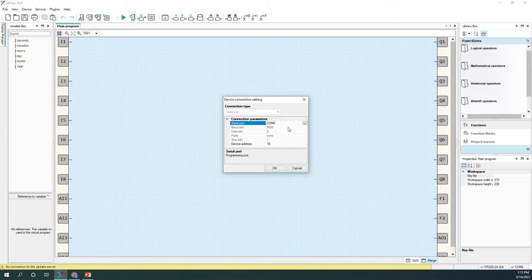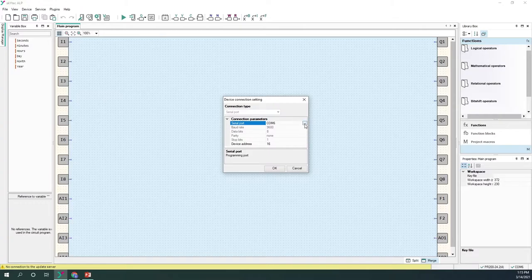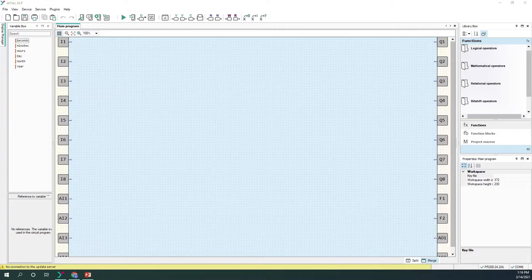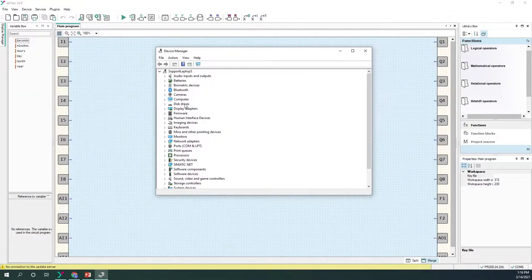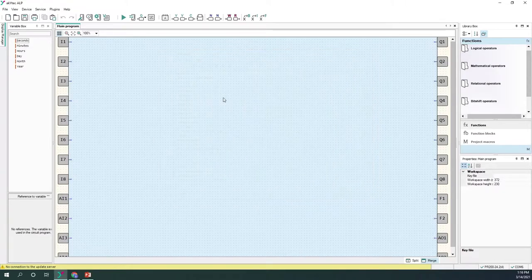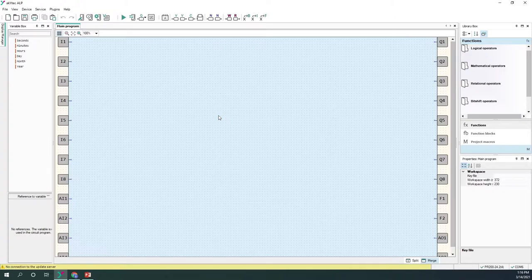On the right side of the screen we can check the connection with the device. Right now the device is connected to serial port number 6, and the device address is 16. If the device is not connected, you can check whether the right serial port has been selected. If you don't know the serial port number, you can click Windows + X to open Device Manager and check to which serial port the device is connected. The blue area in the middle is our workspace — this is where we will create the circuit program.